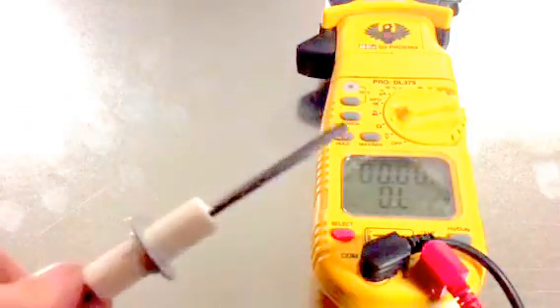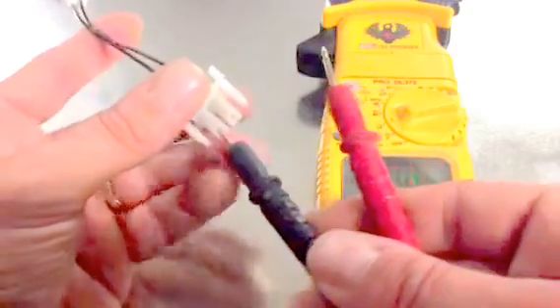Silicon nitride - those are the tough igniters. They sometimes come in a stick form like that we talked about. Now to test these, all we're gonna do is set our meter to ohms like we have and check each side.